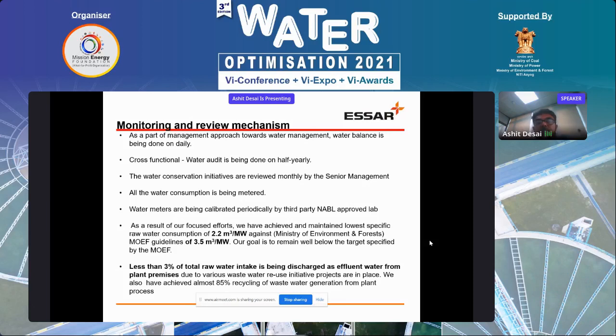As a result of this, we are able to achieve our lowest raw water specific consumption of 2.2 cubic meter per megawatt against the MoEF guideline of 3.5 cubic meter per megawatt. Our goal is to remain well below the target specified by the Ministry of Environment and Forest. With a lot of effort, we are able to discharge less than 3% of total water intake as effluent from our power plant premises. And of the effluent generated, 85% of that wastewater is reused in the plant process itself.